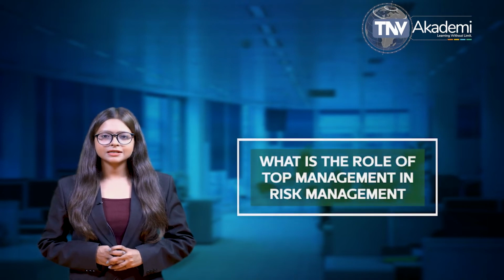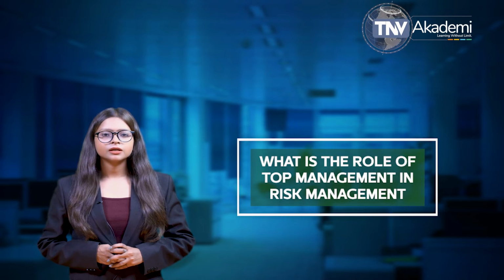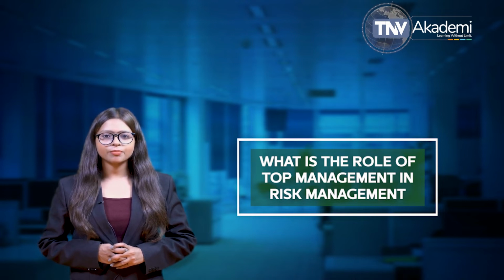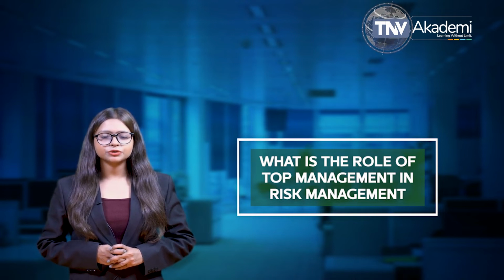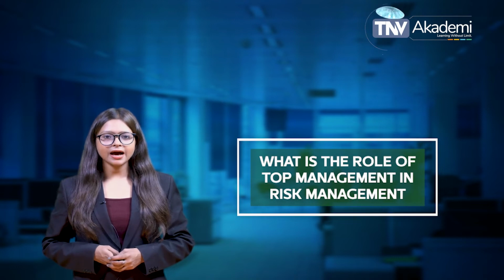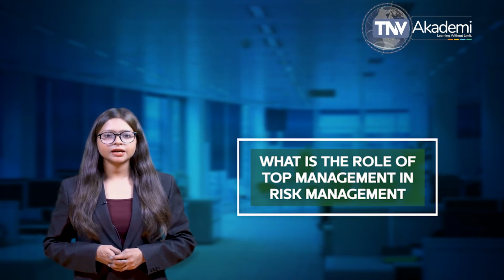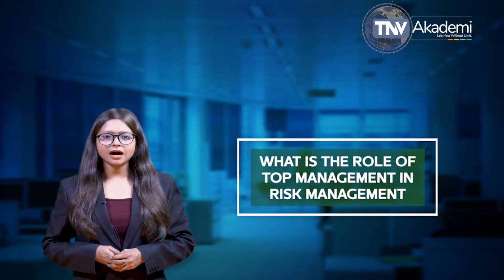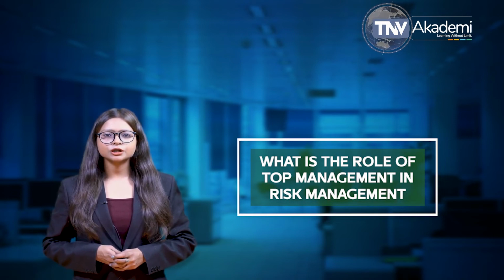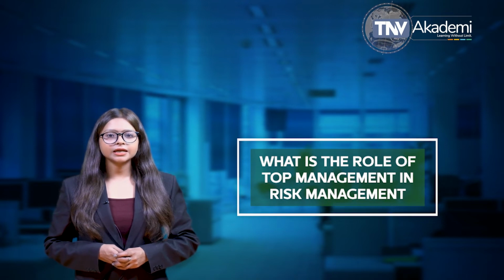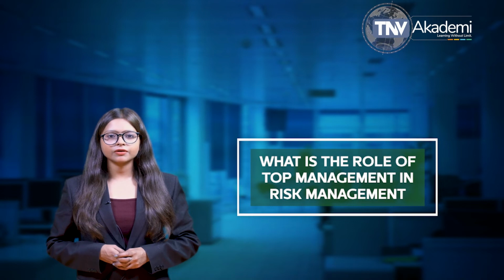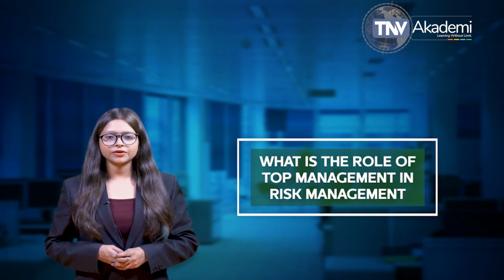We will now discuss the role of top management in risk management. The foundation of the risk management process must be top management. Top management has the responsibility for determining whether the product risks are acceptable or not. Further, they must be responsible for making sure there are adequate and appropriate resources for conducting risk management assessments and that these assessments are effective.